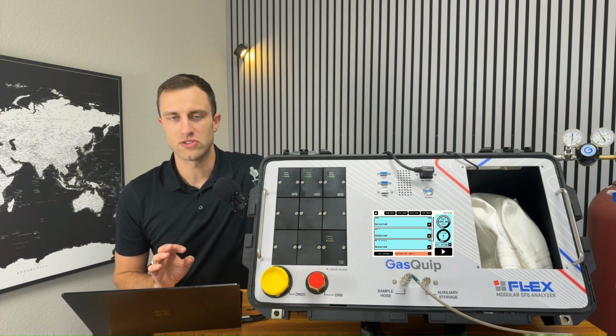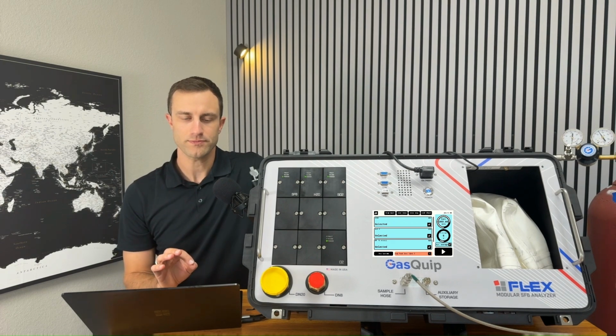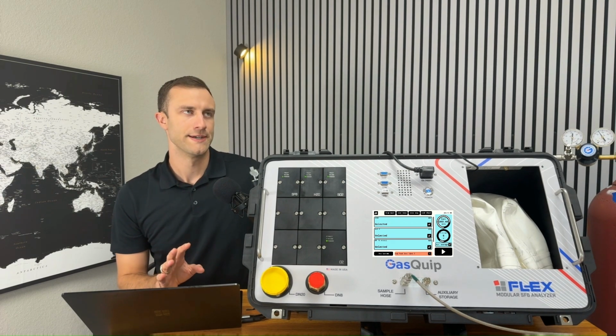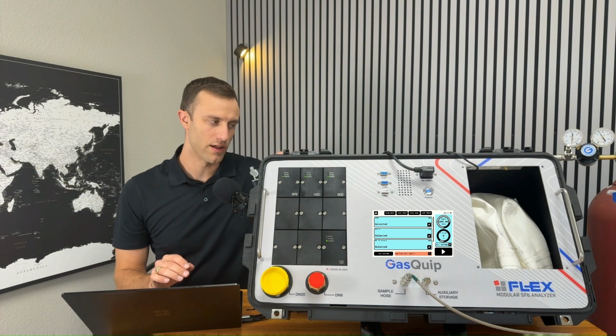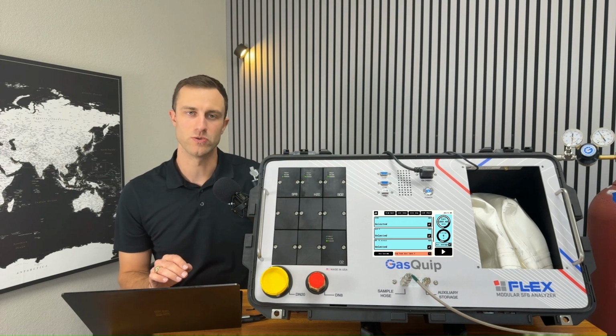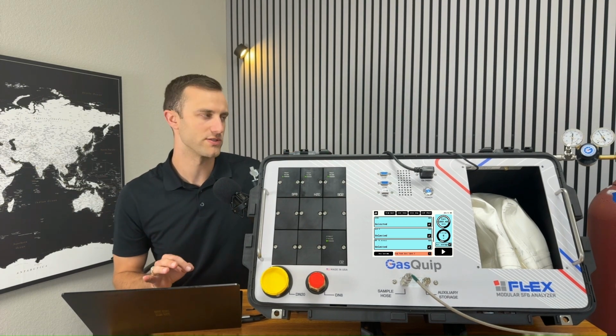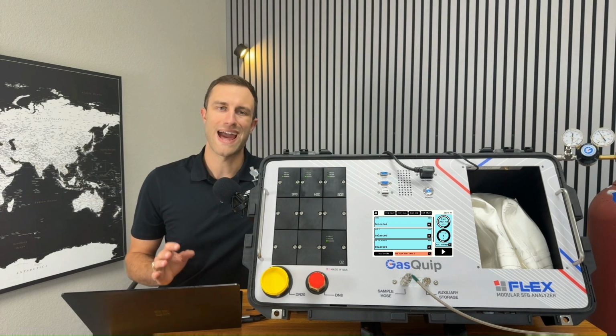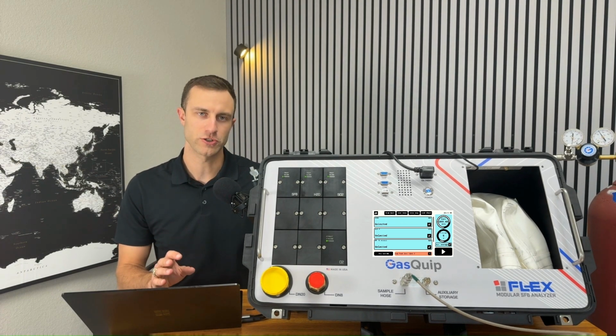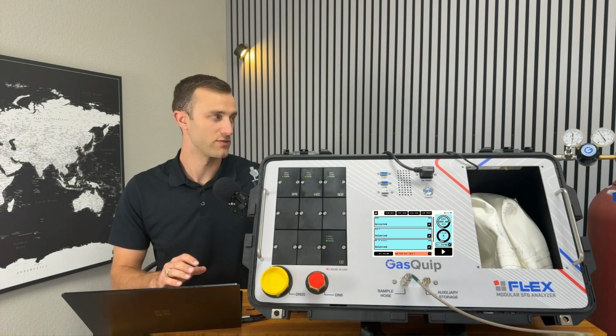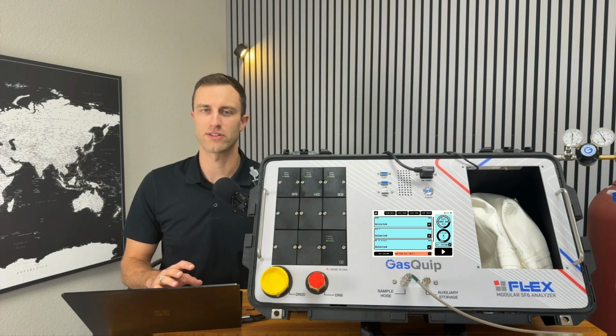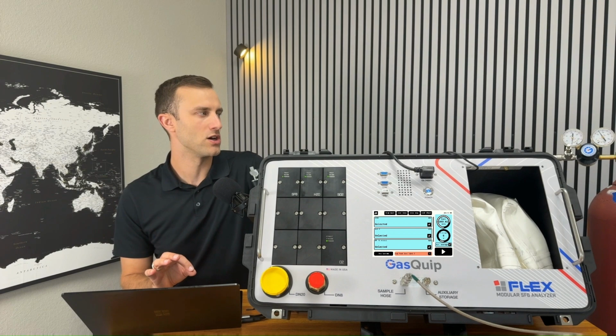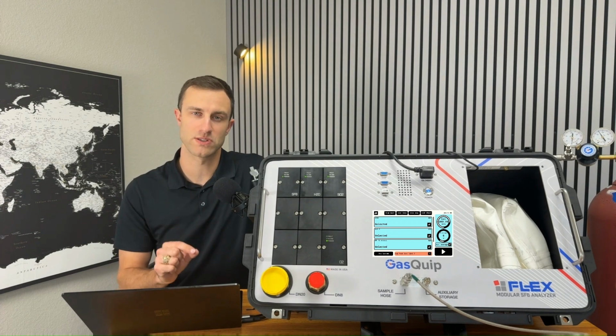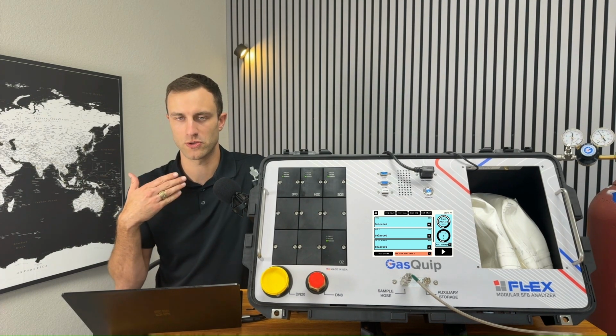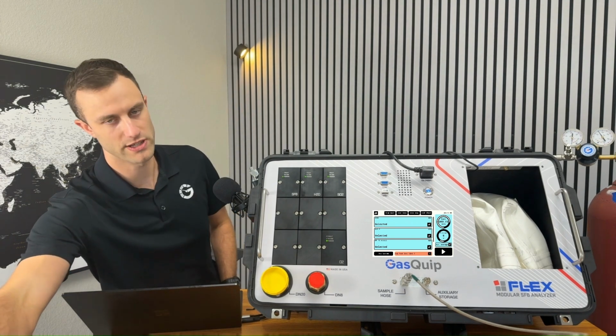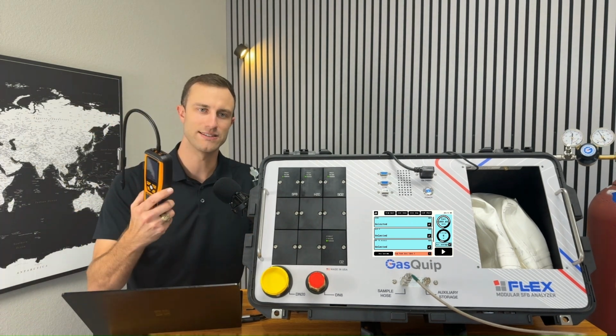The third thing is to make sure you don't have any rubber or any bad connections on the system or on the hose connections themselves. We talked about this earlier, but rubber adsorbs and absorbs moisture and can spike your moisture levels. So if you have any rubber, I would take any of that out of the system that you're testing, and also eliminate as many of the connection points as possible, which would bring us to the third option for troubleshooting, which is to employ a leak detector.